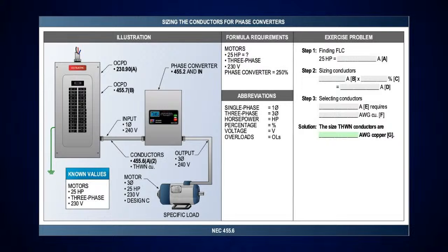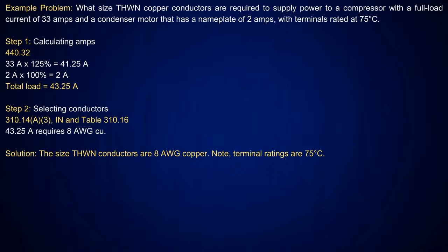That's a good question. Here you got a 25 horsepower motor. You come in and go over to table 430.250. It's a three-phase, and then you're going to take it for 455.6(A)(2) at 250%, and then you're going to size your conductor based on whatever your calculated amperage is. So everybody should be able to follow that just fine.